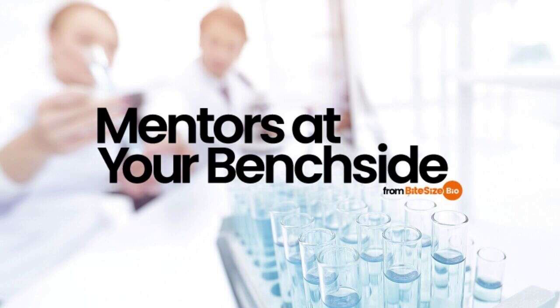Tip number 2. Keep your centrifuge below maximum speed. The maximum speed of your sweet new centrifuge is 26,000 RPM. You pop in some tubes and begin to centrifuge at 26,000 RPM for 20 minutes while grabbing a quick lunch. When you get back to the lab, your lab mates are huddled around the broken centrifuge.